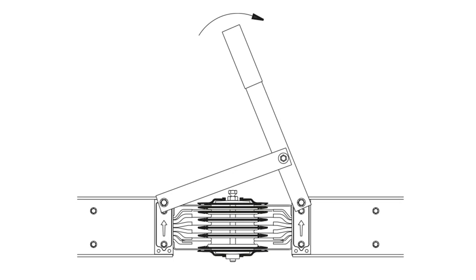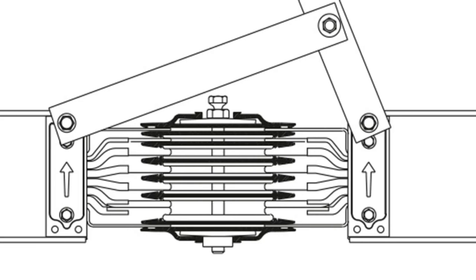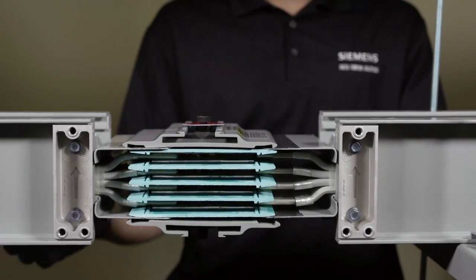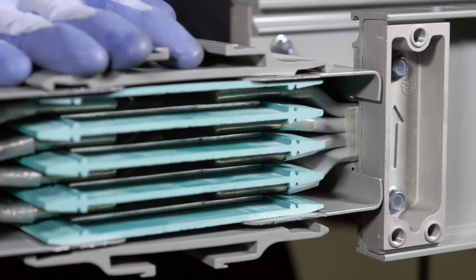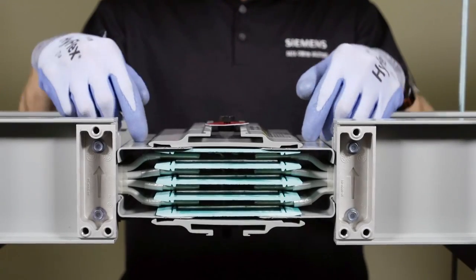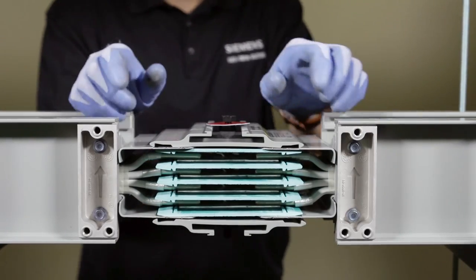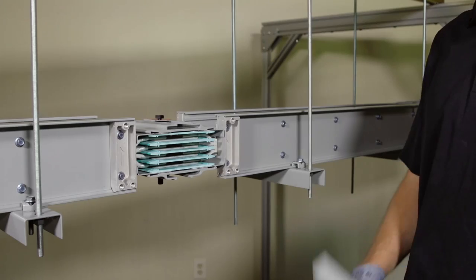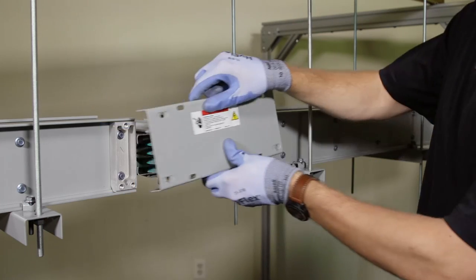For high amperage busway, slide the sections together with the Sentron busway assembly tool until the holes in the joint cover align with the holes in the joint support. For lighter amperage constructions, you can move the pieces together by hand. Carefully align the edges of the joint stack with the edges of the housing and end ramps, then center the joint stack between the joint supports. For busway other than the IP40, pay special attention to ensure the gaskets on the underside of the end ramps are not damaged.